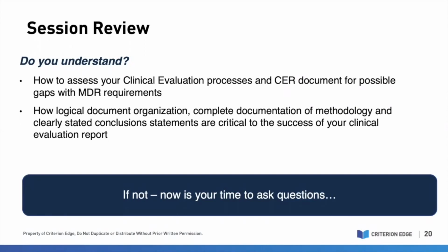That's getting into, again, and I hate to cop out on all these questions, but I want to be really careful and make sure that we clearly communicate to you, our audience, that we don't do strategy discussions. The accessories can be included or referenced within a CER, and data on those accessories can be used in the CER, but only when those accessories are used only with the subject device under evaluation.